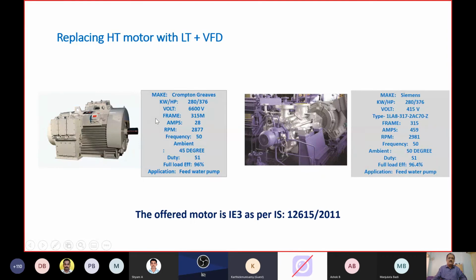The existing motor was a 280 kilowatt, 6.6 kV medium voltage motor, which we otherwise call an HT motor, in 315 M frame size. So what we did was we replaced it with the same 280 kilowatt LT 415 volt motor, same frame size 315. Efficiency improved marginally, from 96 to 96.4, but this efficiency is accurately measured, unlike the earlier efficiency, which is based on assumed stray losses of 0.5%, as you can imagine.